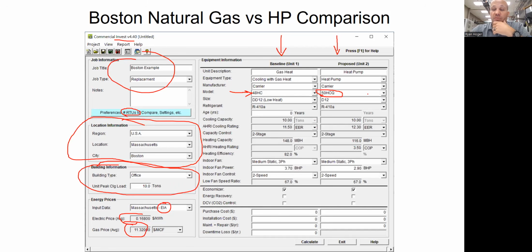So in this case, I'm picking them from the drop down by model number. There's also the ability to put in a user defined unit where I say, I got this weird thing, I don't even know what it is, and then I have to type in all of its old AHRI data from 20 years ago. But if it's one of the ones in the drop down, which I believe are Trane, Carrier, Lennox, and York as defaults, I already know that information on there. And I could tell it if I had any accessories. In this case, I'm telling it I want to put in a brand new unit at this efficiency level. I want to get a 2-speed fan, which is required by code in your state right now for this size unit, and I want to get an economizer, also required by code. And on the heat pump version, I'm also going to do those things because they're required by code, right? But I'm getting a heat pump version.